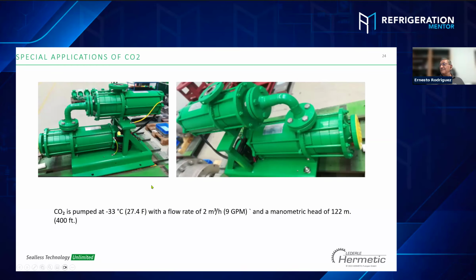Yeah, this is for when you have a very long distance or the process requires a very high head of the pump and very low flow. You see the flow is very low, so to prevent flashing gas inside the pump we need to use this type of application. Maintain the flow running across the pump for cooling, and maintain the high differential pressure.